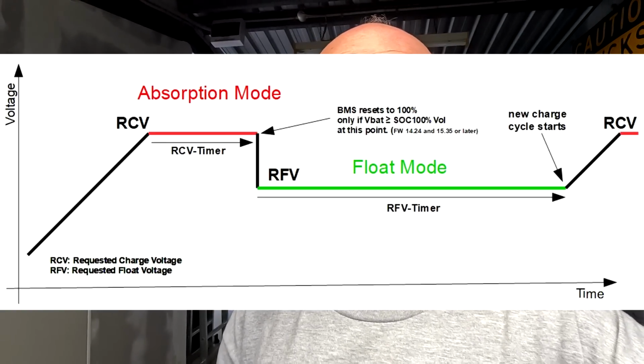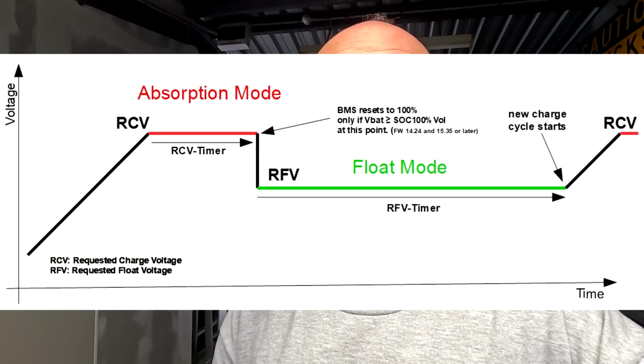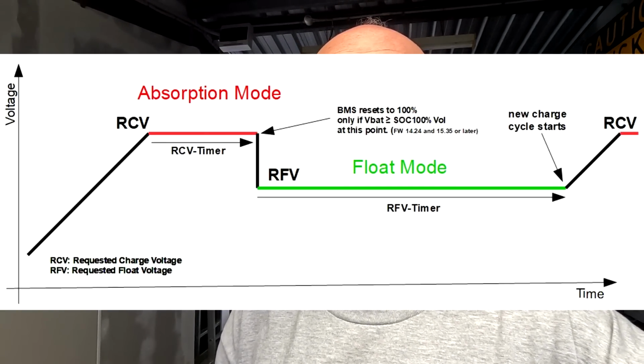This behavior actually causes degradation in the battery. Once the battery is fully charged, you should really lower the voltage, go down to 3.35 volts and hold it there. But cycling it at the highest point—2 minutes charging, 2 minutes discharging—I'm not a fan of that.